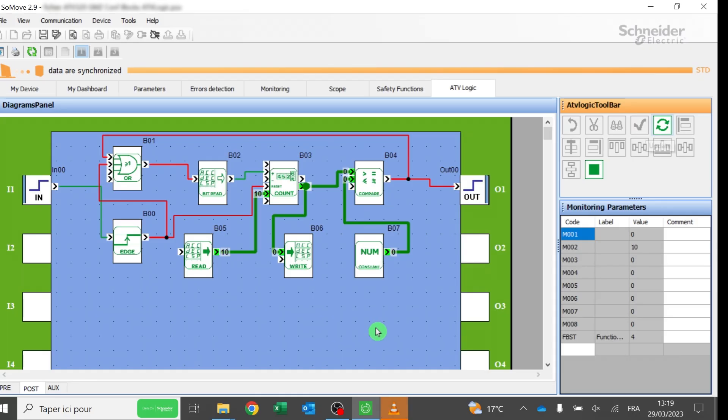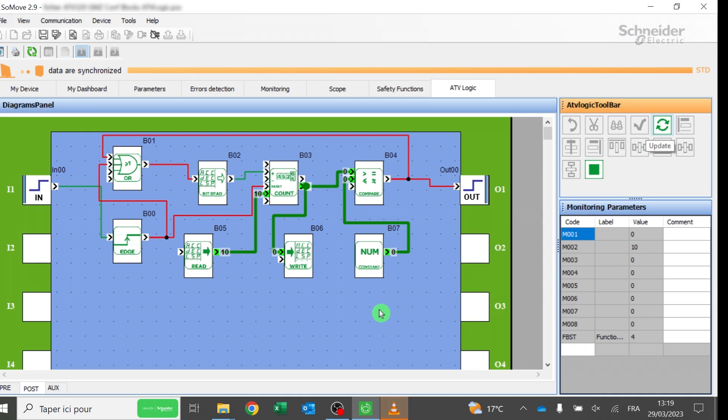In this example, the virtual logic input I1 of the ATV logic program is assigned to DI1, hardware digital logic input number 1 equals LI1. I1 signal is assigned to an edge front to avoid hazardous movement. The output of the front edge function is linked to a load input of a count function block.